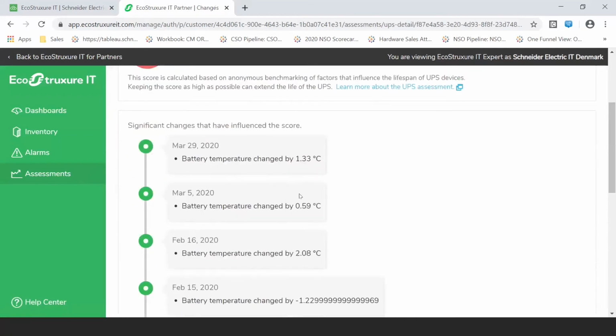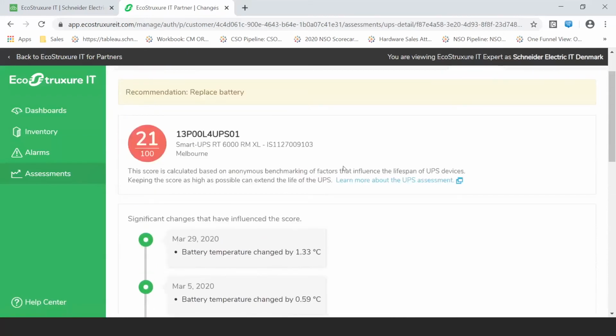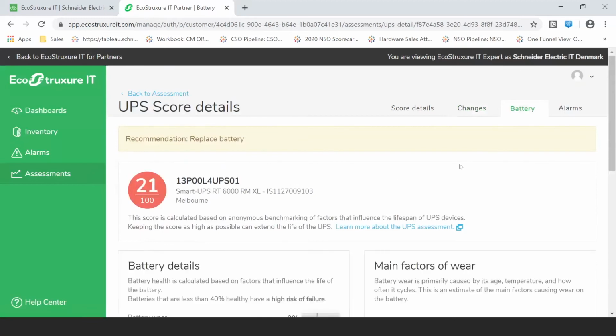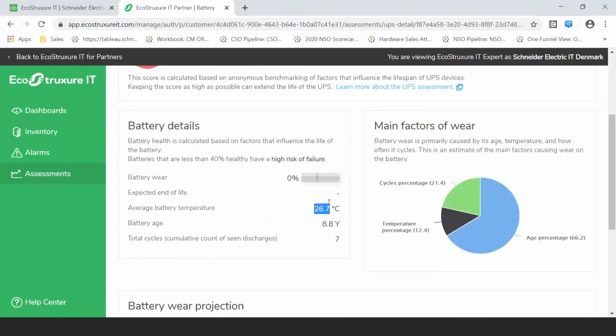The battery temperature has been changing and increasing. We can look specifically at the battery itself, and if you look at a 26 degree Celsius temperature, that's an average—you're looking at about 80 degrees Fahrenheit or over, which is too warm to be housing a lead acid battery. We give you statistics on the main factors of wear: age being the number one reason for a UPS dying, temperature being a close third, and cycles being second—the number of times a UPS is cycling, turning on and off.